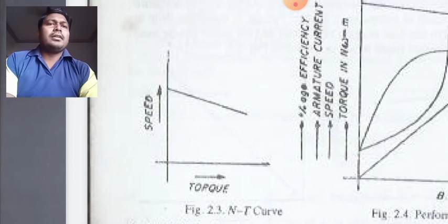Performance curve. Now students, the curves for efficiency, speed, torque and current plotted against BHP of a motor are called performance curves. The performance curve for a shunt motor is as in the diagram. From the speed BHP curve, it is seen that the motor has a definite speed at no load, and hence it cannot run away when the load is suddenly thrown off. Also, there is a slight fall in speed from no load to full load, and hence the motor can be used when a substantially constant speed is required.